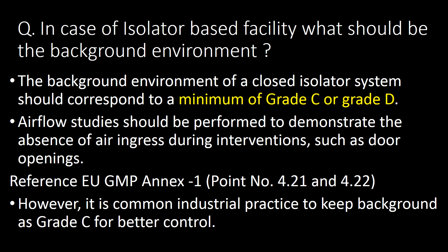In case of an isolator-based facility, what should be the background environment? The background environment of a closed isolator system should correspond to a minimum of Grade C or Grade D. Airflow studies should be performed to demonstrate the absence of air ingress during interventions such as door openings. Reference: EU GMP Annex 1, Point No. 4.21 and 4.22. However, it is common industrial practice to keep the background area as Grade C for better control.